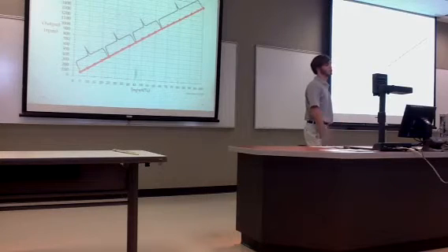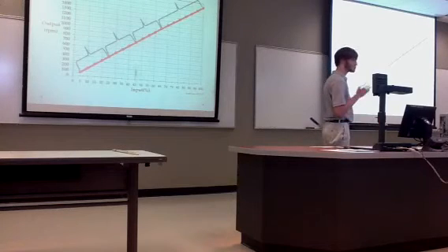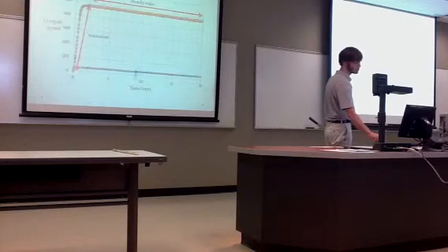Our steady state operating curve is almost perfectly linear. It gets a little bit squirrely below about 5%, and toward 95% when the motor starts to hit overpower a little bit, but generally it's linear. So for any input, you can just use a standard y equals mx plus b equation to find the given output.